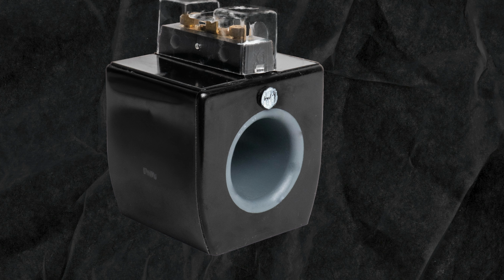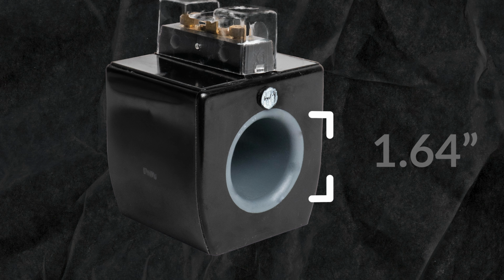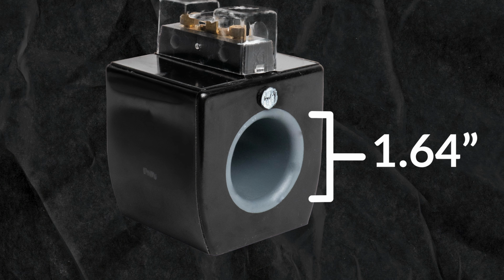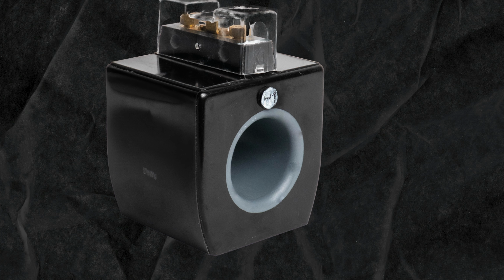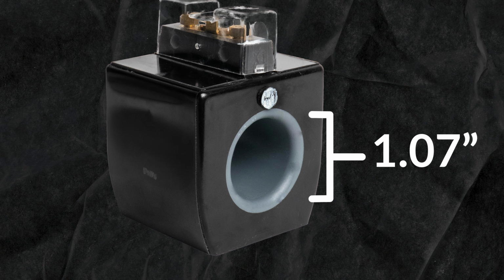The COS CT is typically used in metering cabinets or trans sockets. The diameter of the COS current transformer is 1.64 inches, with the exception of the 200 and the 400:5 CTs. Now those have a 1.07 inch diameter.